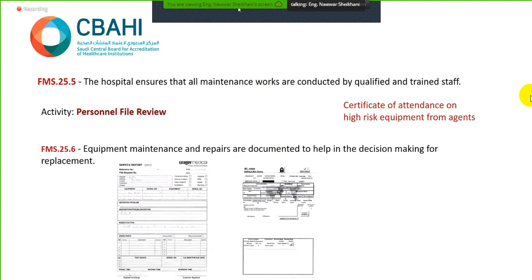25.7: investigation procedure conforms to manufacturer instructions. Here we compare corrective action taken against medical equipment failure. However, PPM frequency is usually based on certain criteria — the major ones being manufacturer recommendations, risk level of the device, and load of work on the device. If you have force one, it's okay, you're welcome to add it. The last criterion is whether there is an equipment recall.